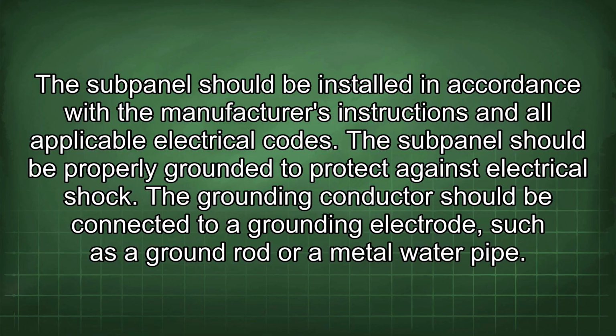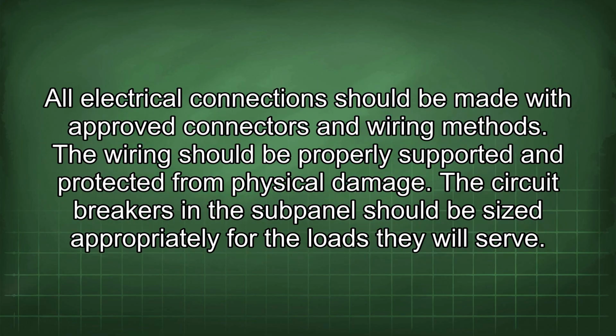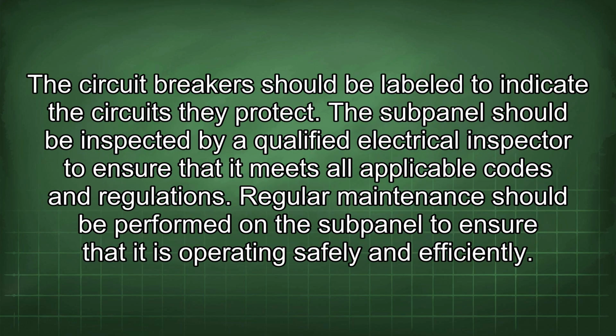The subpanel should be properly grounded to protect against electrical shock. The grounding conductor should be connected to a grounding electrode, such as a ground rod or a metal water pipe. All electrical connections should be made with approved connectors and wiring methods. The wiring should be properly supported and protected from physical damage. The circuit breakers in the subpanel should be sized appropriately for the loads they will serve. The circuit breakers should be labeled to indicate the circuits they protect.